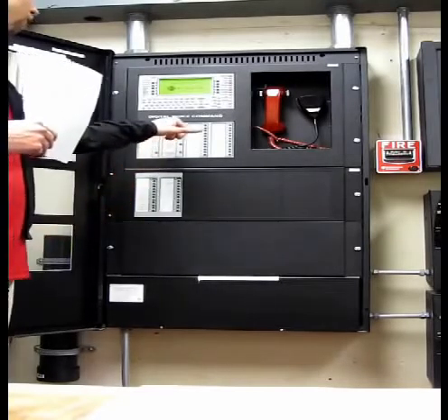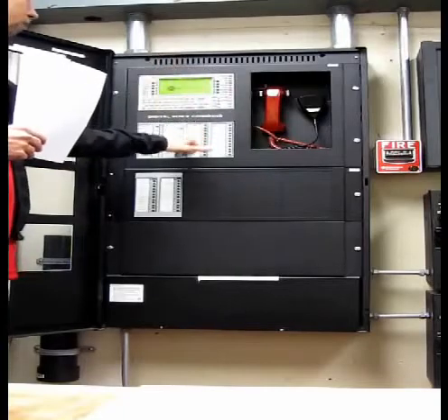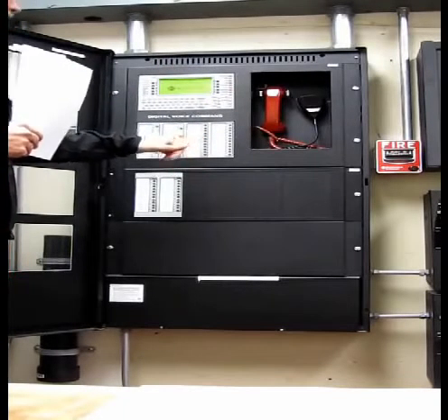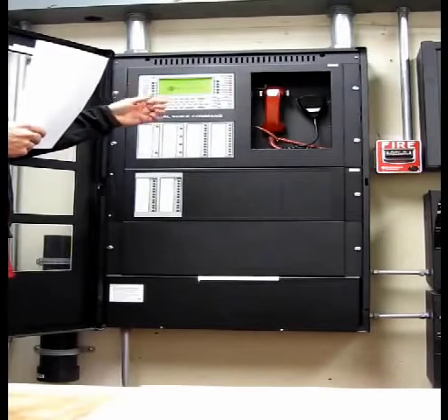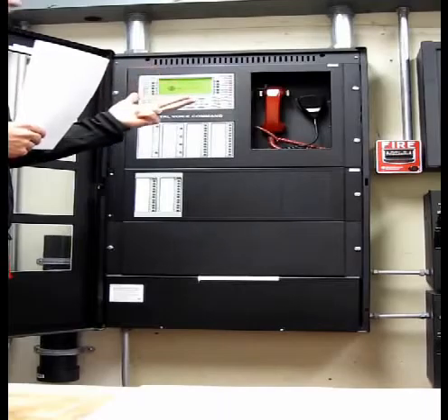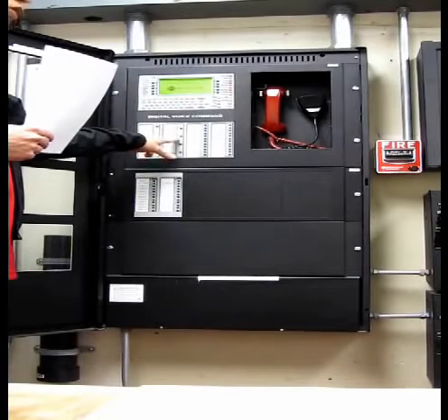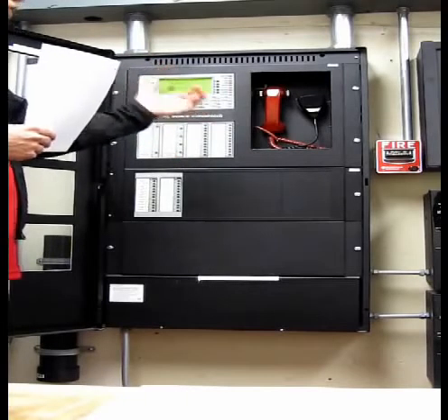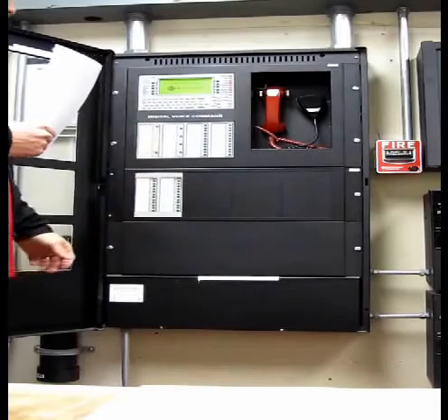Okay, so all call. You pick up the microphone, hit the all call button. Once you key up the mic, you'll be talking to every speaker circuit in the building. If the building is in alarm and you have a floor, let's say the 3rd floor, for example, you're going to have 3rd, 2nd, and 4th in alarm. The speakers will be going off and the strobes will be going off. If you hit this button, page active evac areas, it'll just page those specific floors, and that's an easy way to call off people in a false alarm situation.